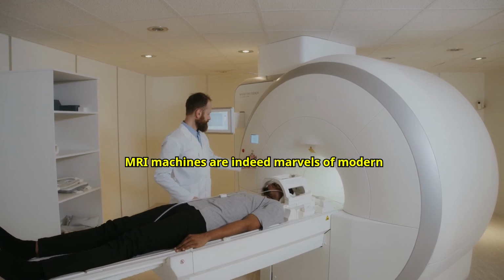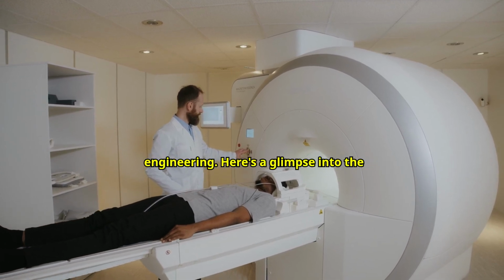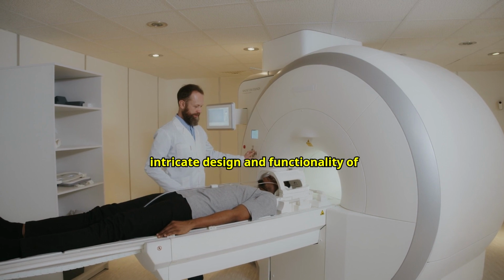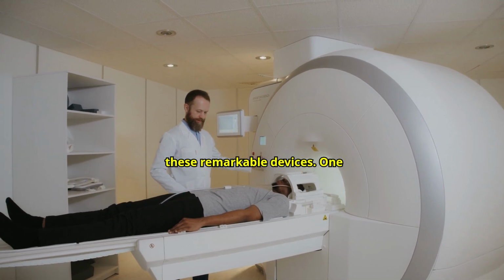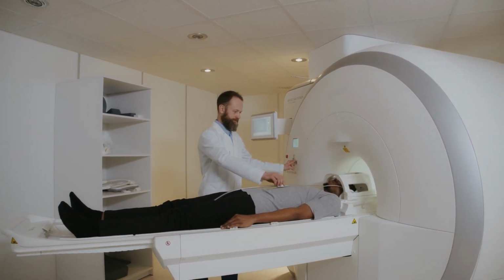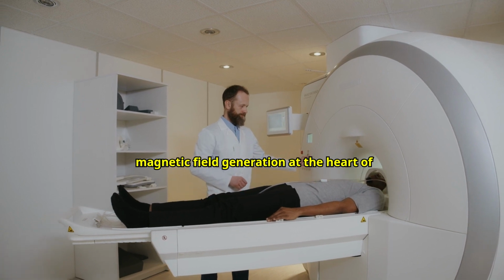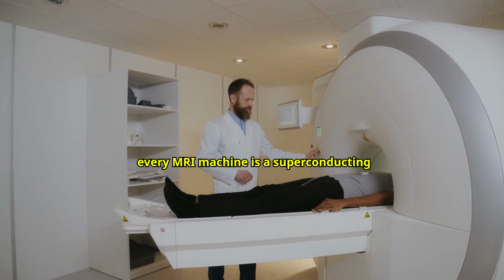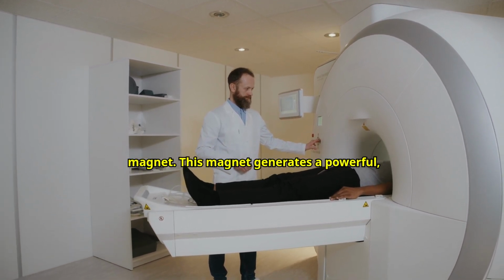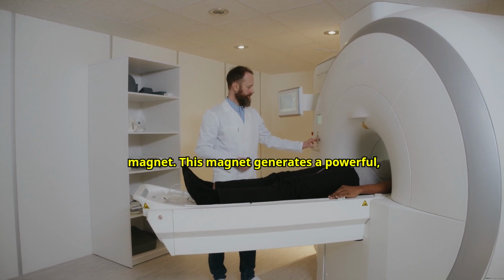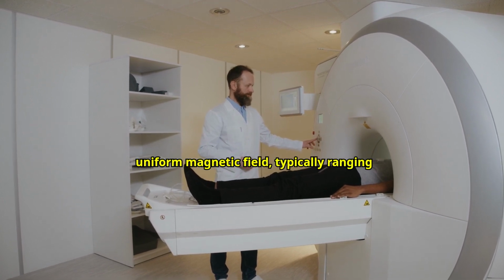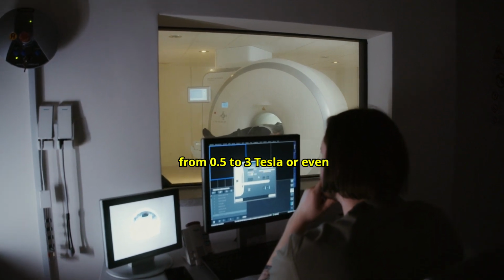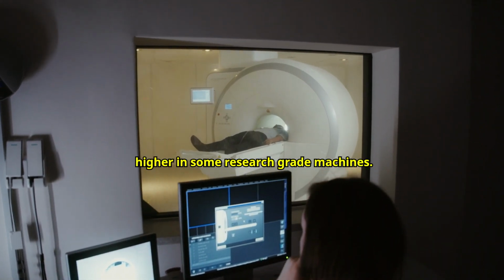MRI machines are indeed marvels of modern engineering. Here's a glimpse into the intricate design and functionality of these remarkable devices. 1. Magnetic field generation. At the heart of every MRI machine is a superconducting magnet.